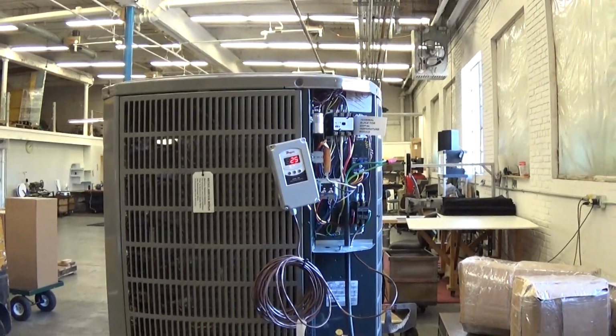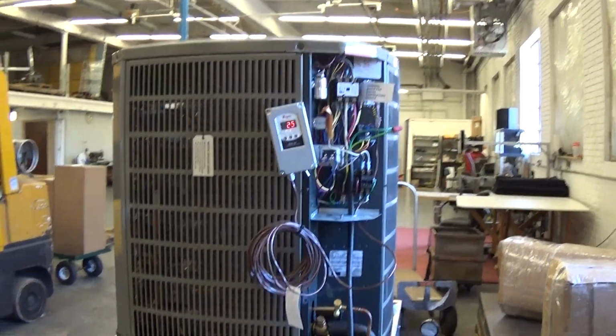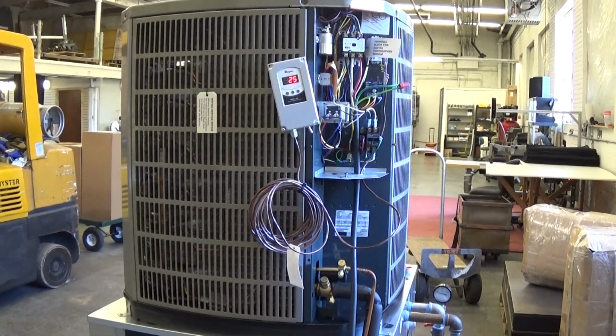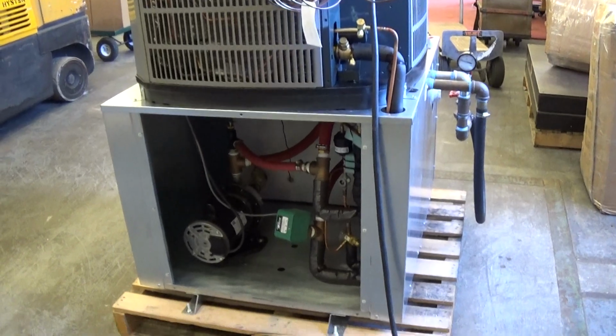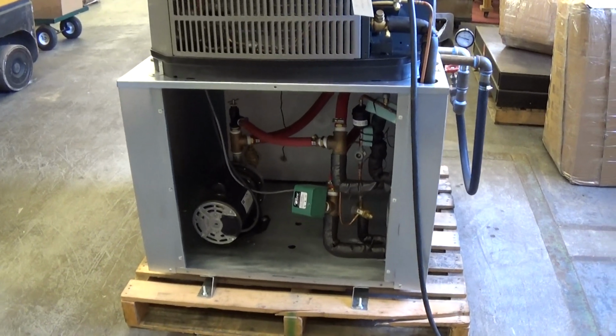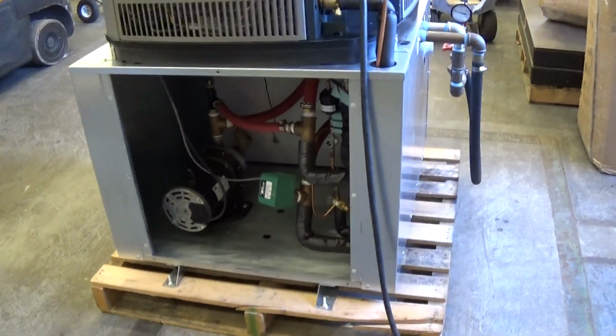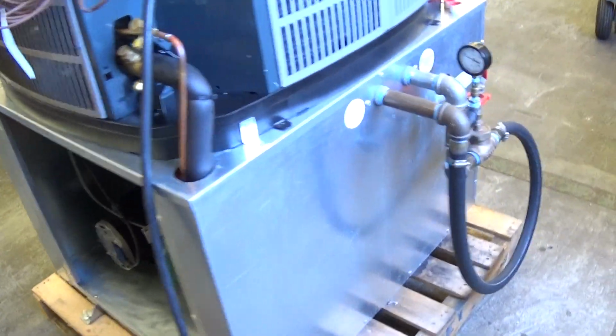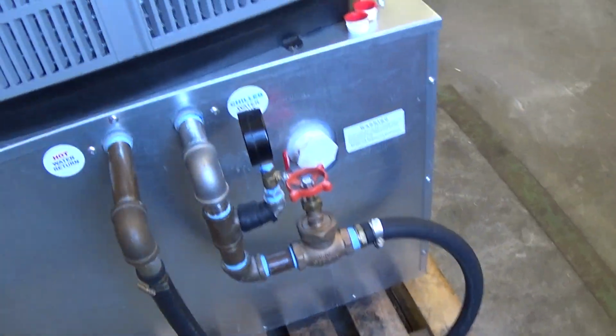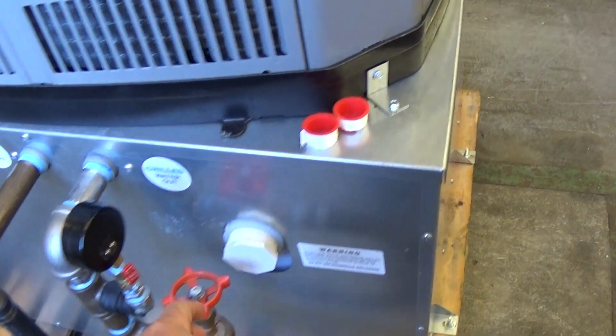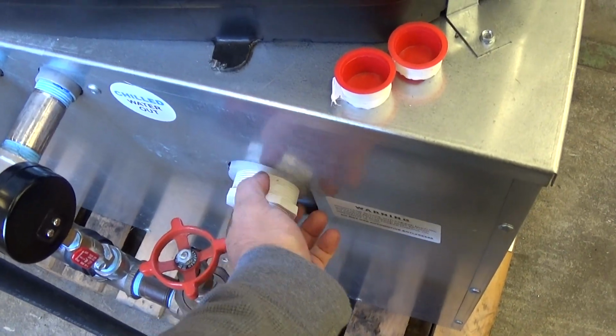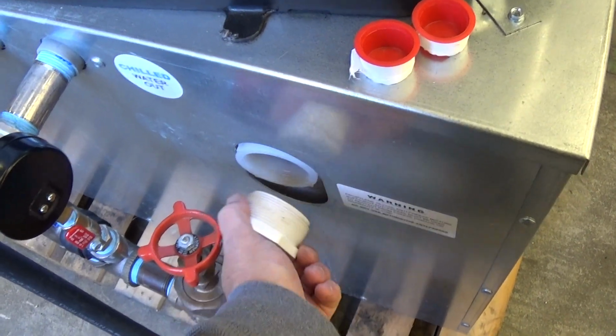In such a case, we want you to run a 40 to 45% glycol concentration in the reservoir. That's a 30-gallon reservoir there. For a glycol application, it will be insulated. On the side of the unit here, you have a nice threaded filler and viewing point for the glycol reservoir.